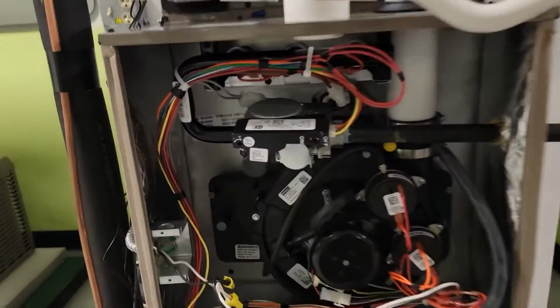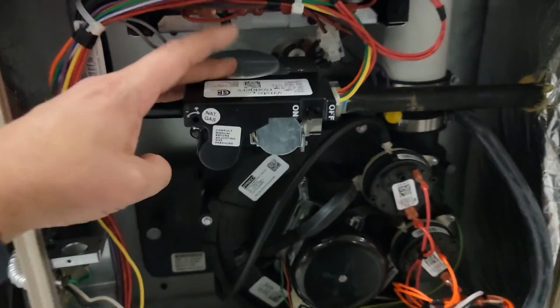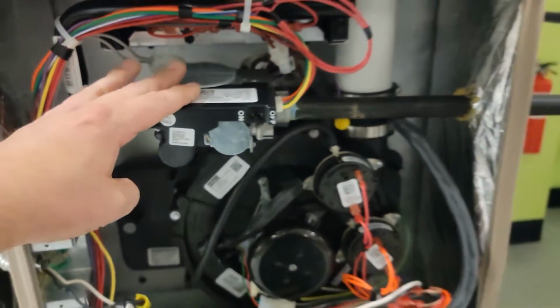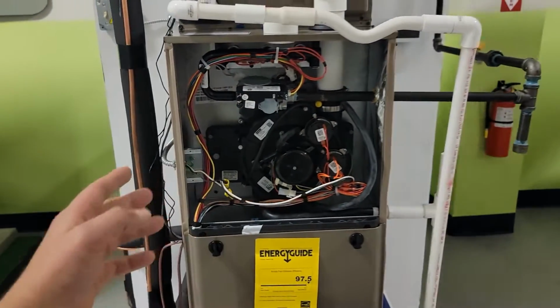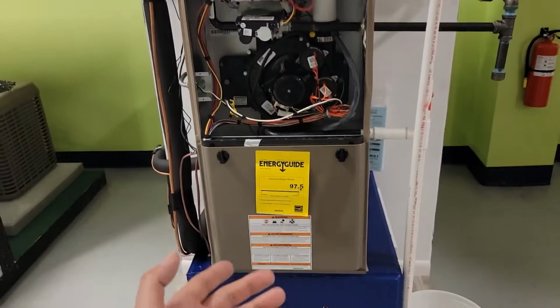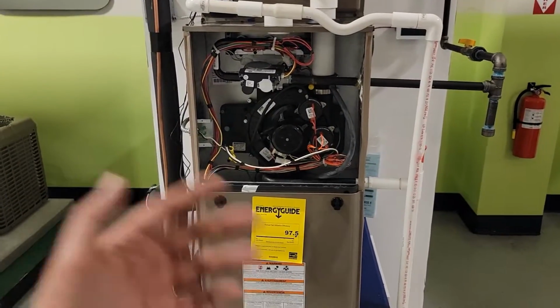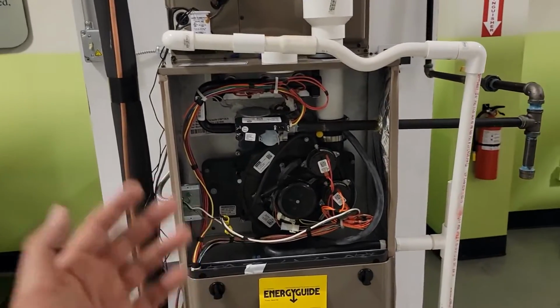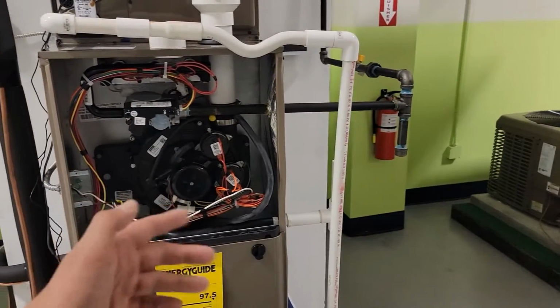Now, this right here is not a two-stage. This is actually a 100% modulating gas valve. So it's able to burn from a very, very low setting all the way up to a high setting, and it's just determined on demand and runtime, okay? So that's the difference in the gas pressure, single stage, two stage, and then modulate. You want to learn how to check gas pressure on a furnace to set the gas pressure? Check out my playlist, HVAC Tips for Technicians. I've got a video on there on how to use a manometer, check and set gas pressure.